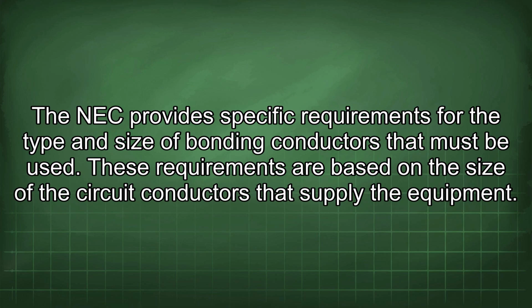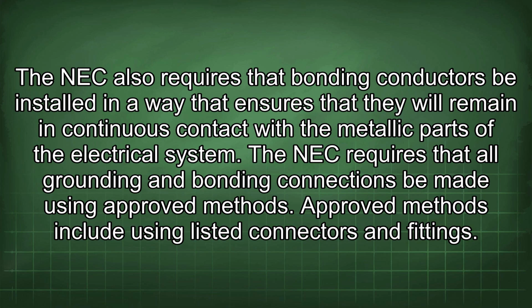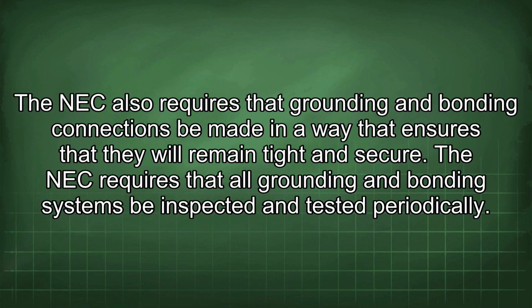The NEC provides specific requirements for the type and size of bonding conductors that must be used. These requirements are based on the size of the circuit conductors that supply the equipment. The NEC also requires that bonding conductors be installed in a way that ensures that they will remain in continuous contact with the metallic parts of the electrical system. The NEC requires that all grounding and bonding connections be made using approved methods. Approved methods include using listed connectors and fittings. The NEC also requires that grounding and bonding connections be made in a way that ensures that they will remain tight and secure.